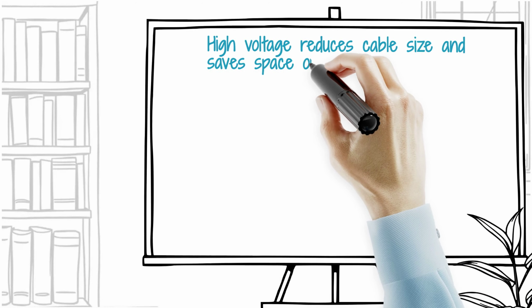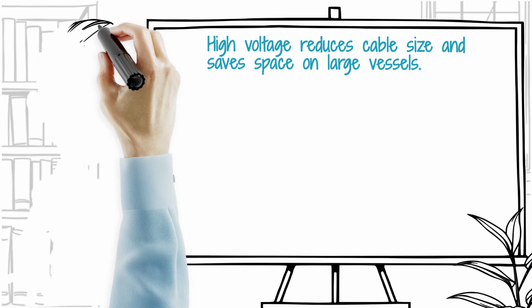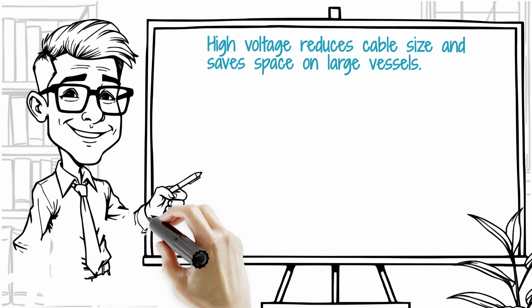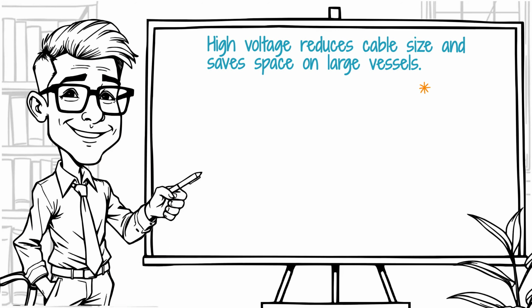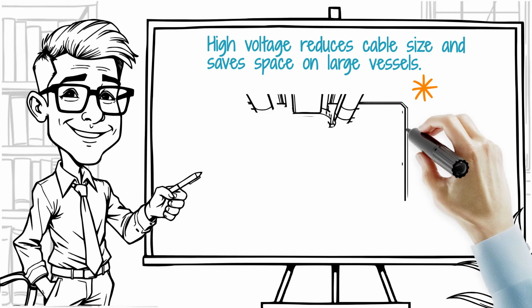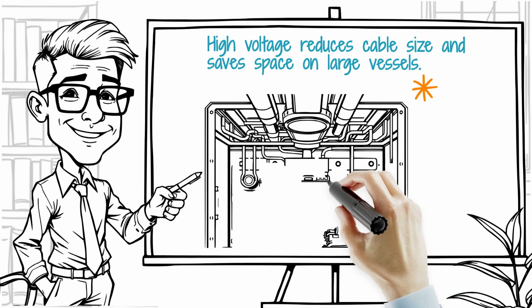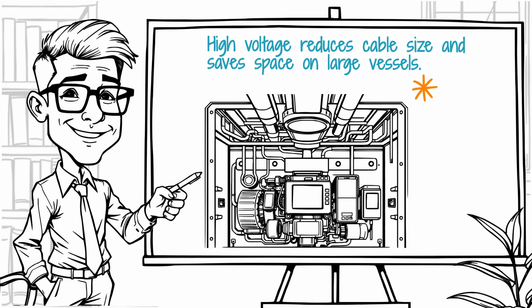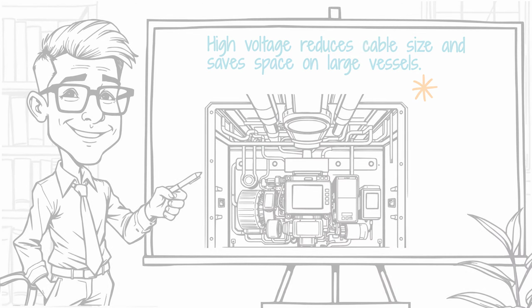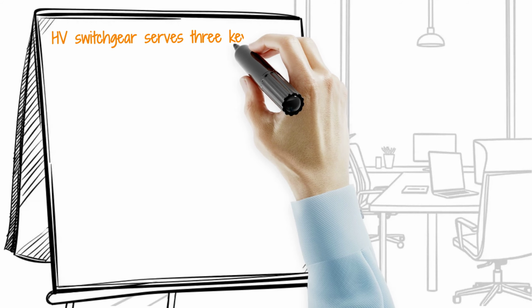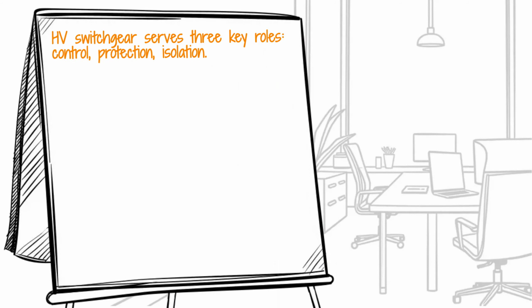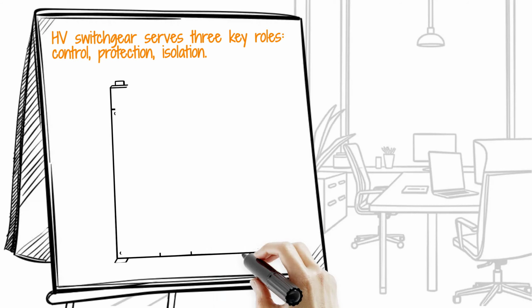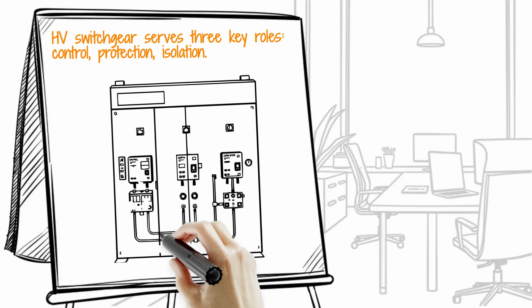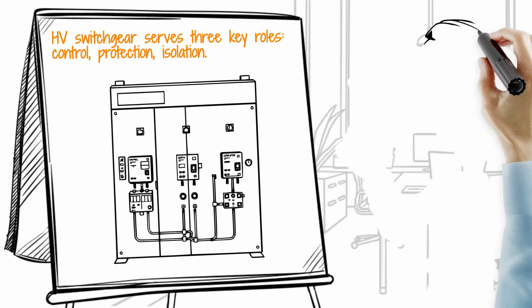The HV switchgear is the central hub for this power. It is an organized assembly of circuit breakers, switches, fuses, and associated control and protective equipment that controls, protects, and isolates the electrical equipment. Its three primary functions are control, protection, and isolation. Control involves connecting and disconnecting the main generators, large motors like propulsion motors or large thrusters, and high-capacity feeder circuits.